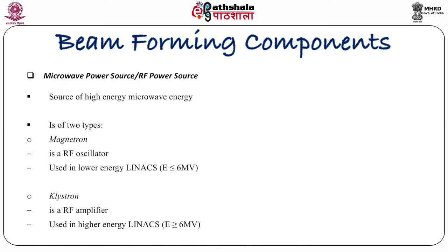The microwave power source, or RF power source, is the source of high energy microwave energy. With the help of this, electron energy is increased. It is of two types: the magnetron, which is an RF oscillator used in lower energy linear accelerators, and the klystron, which is an RF amplifier used in high energy linear accelerators when the energy is more than 6 MeV.